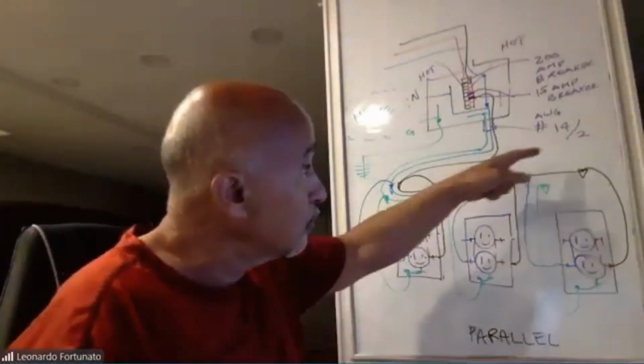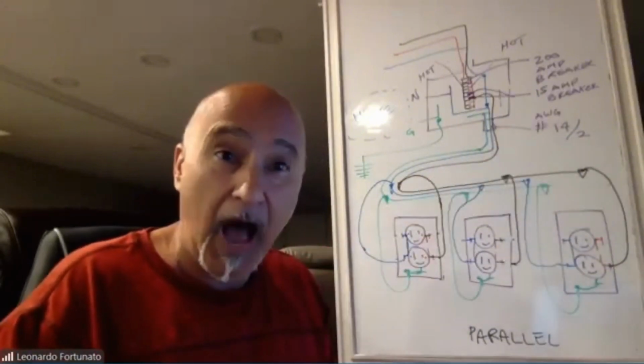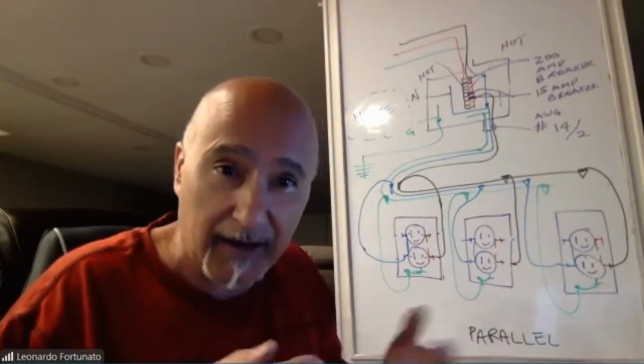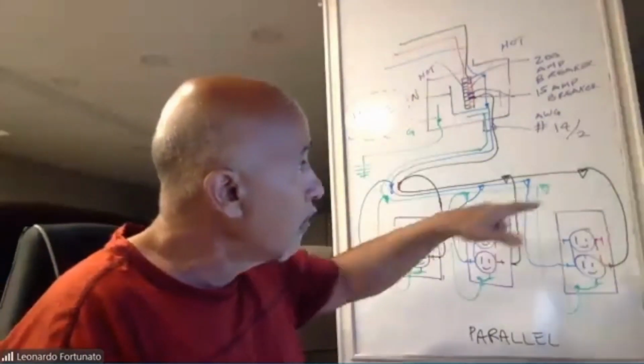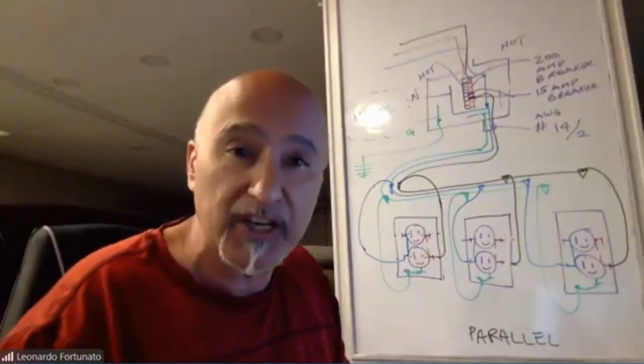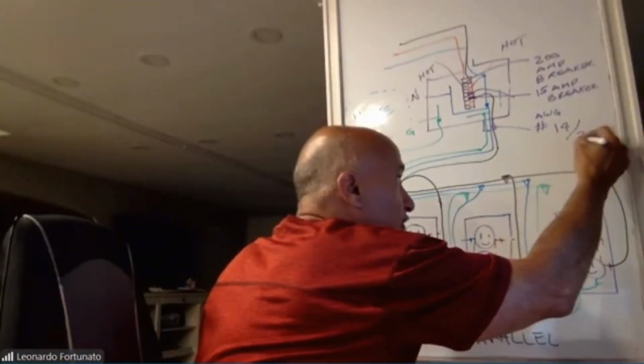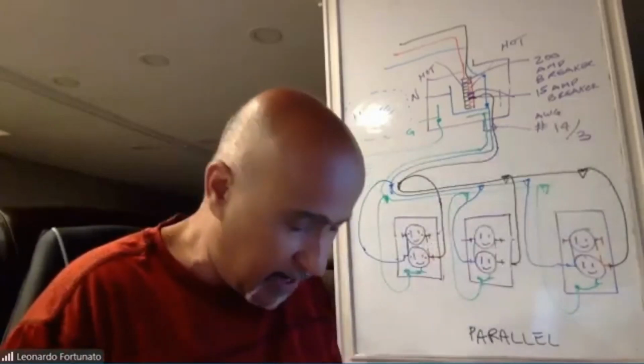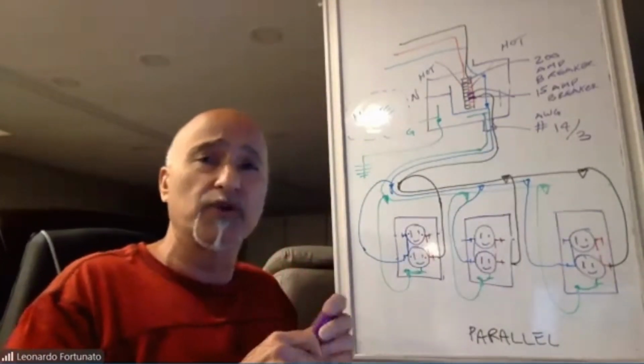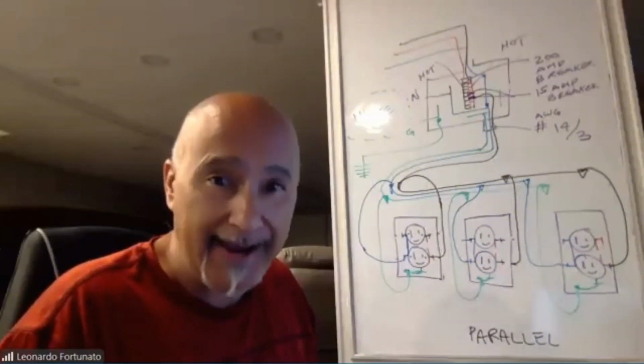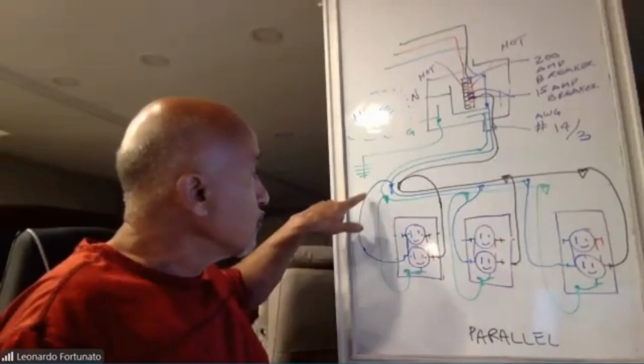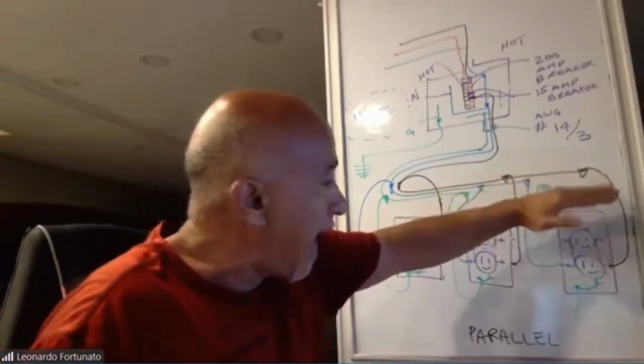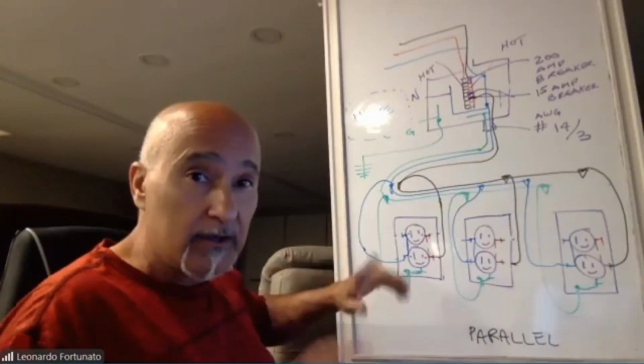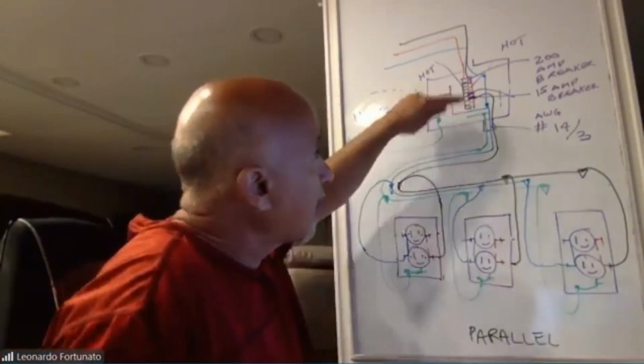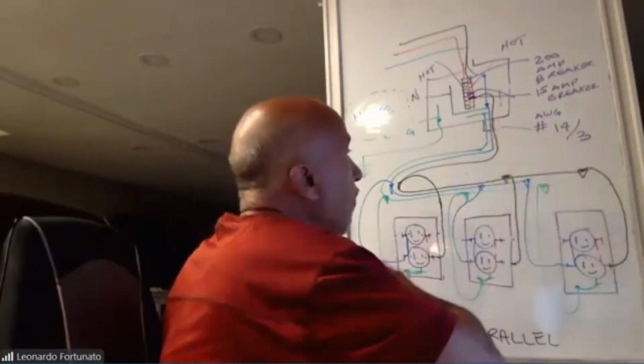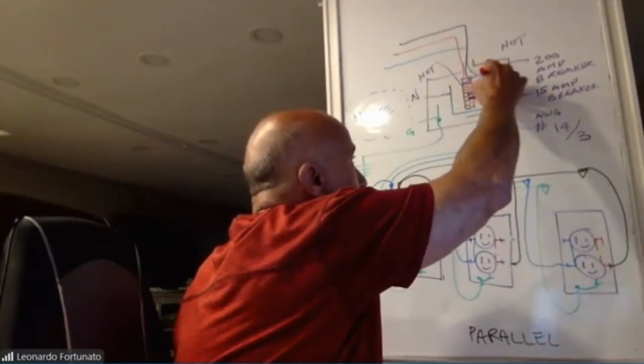Instead of using two 14-2s, ladies and gentlemen, I can use a wire that has 3 conductors. So instead of using 14-2, I'm going to use 14-3. If I use 14-3, how many conductors do I have in that cable? 3 conductors. And what would be the color of those conductors? Red, black, and white. Fantastic. We've already used the white neutral. We already got our black power going to the bottom. What we're going to do now is, to the second breaker, now that we're using 14-3, we're going to bring the red wire to that breaker.